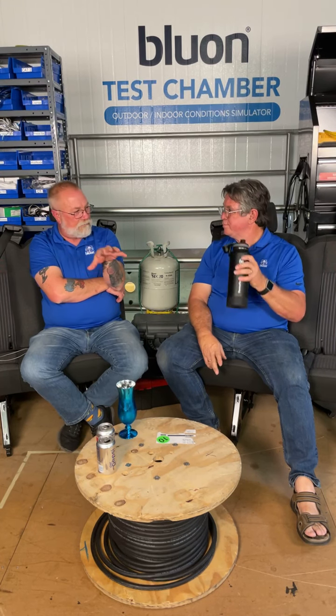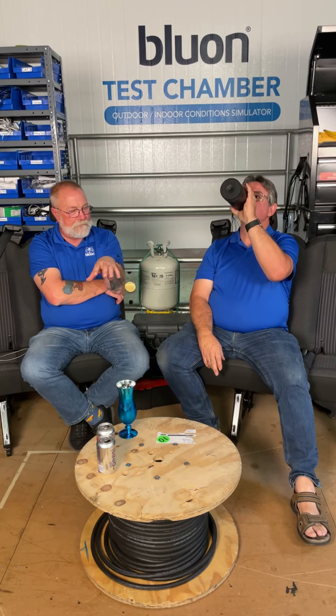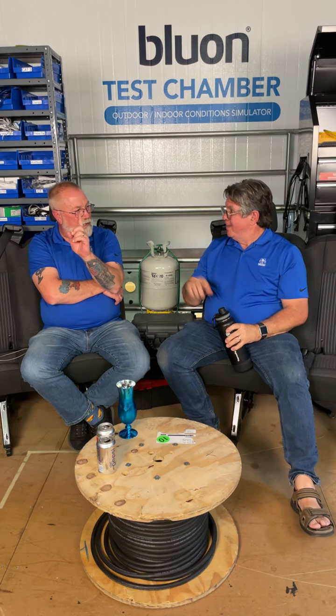All signs pointed back to the board. They accept. Once we got to the accept, then it's like, okay, now you've got to start at the board. And yes, he had 24 volts leaving the board. He did not have 24 volts coming back. And it's like, you've got to find it. It's in that machine someplace. You've got 5 safeties in that machine, and you've got to find them all.